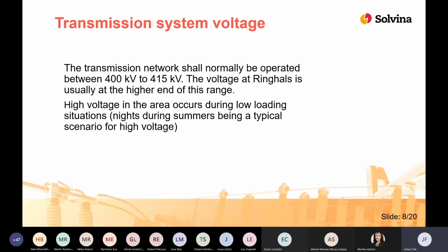From the demands on the TSO, the transmission system shall be operated between 400 and 415 kV. From the data we could see that the voltage in the area is typically at the higher end of this range. We can also see that on several occasions it has been well above 415. We will look at one of these instances later in the presentation. High voltage is typically more common during low load situations, and vice versa, low voltage during high load.